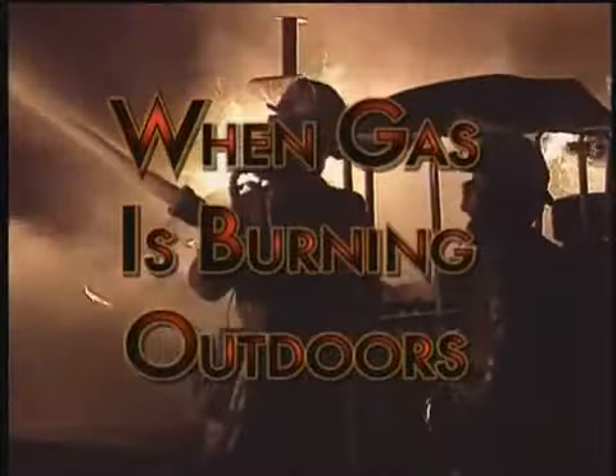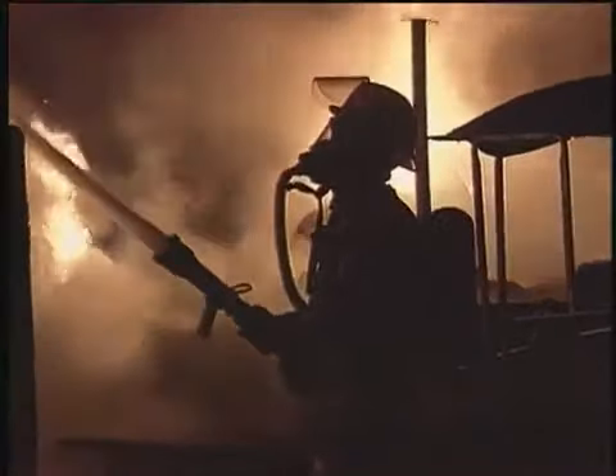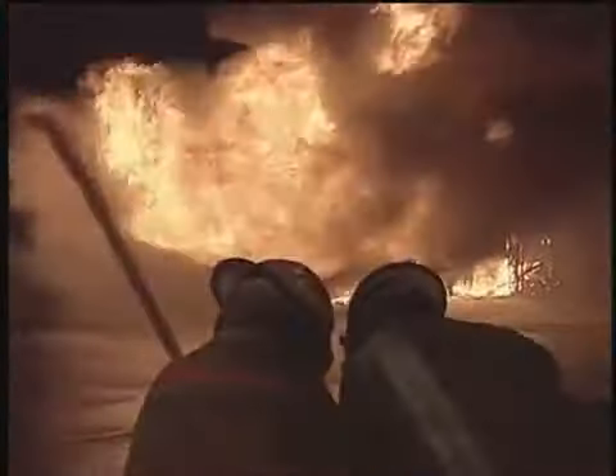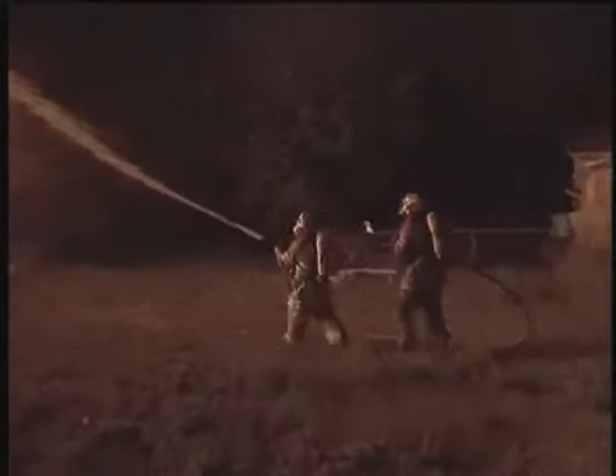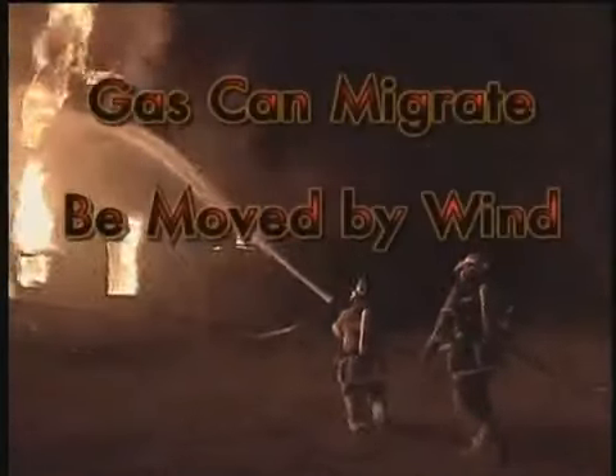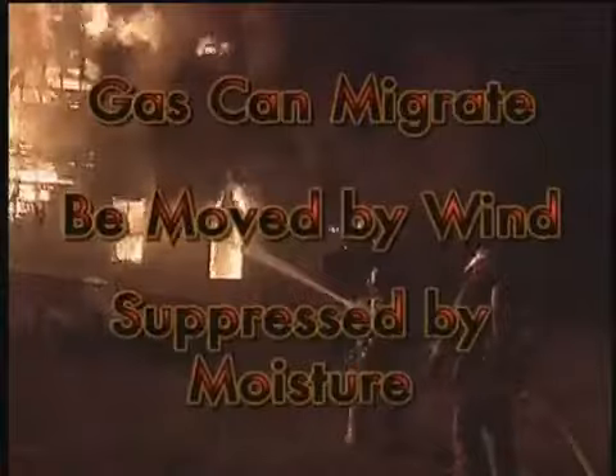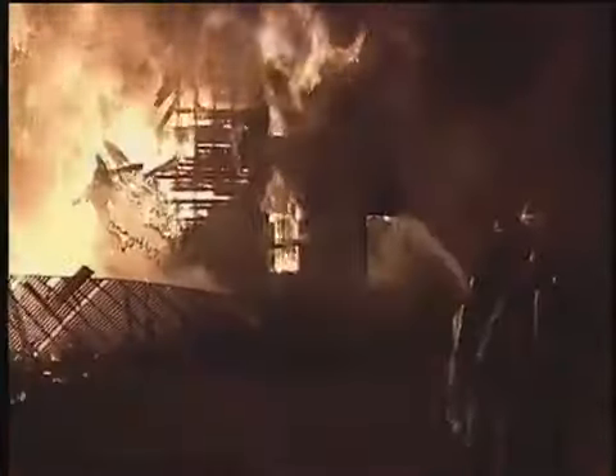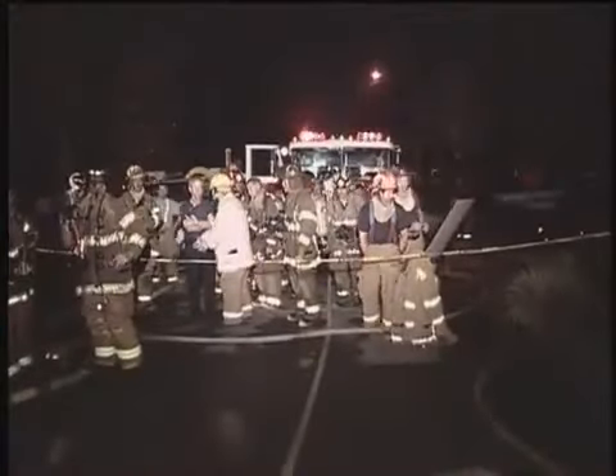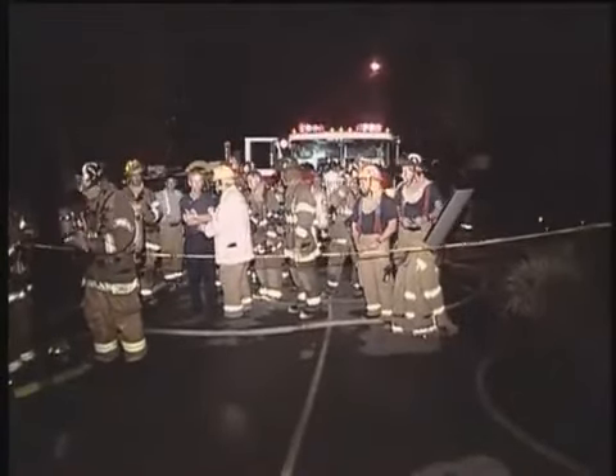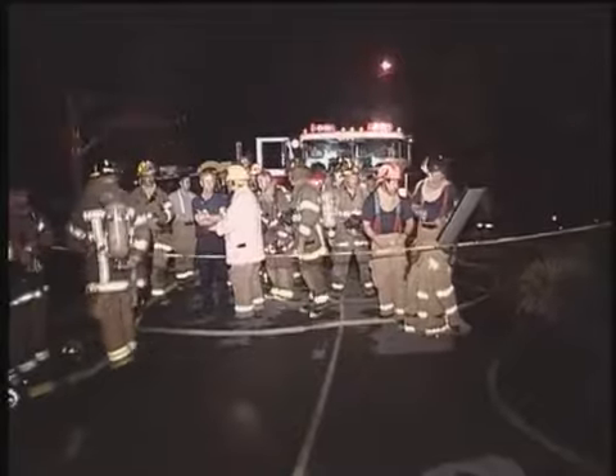When gas is burning outdoors, clear thinking is critical because you're dealing with multiple factors and exposures which all have to be accounted for. Rushing into action too quickly can be a recipe for disaster. Always keep in mind that gas can migrate, be moved by wind, or suppressed by moisture. So utilize your senses and be sure you're upwind of the gas fire. This factor extends to how you make the entire area safe through evacuation and site control measures.